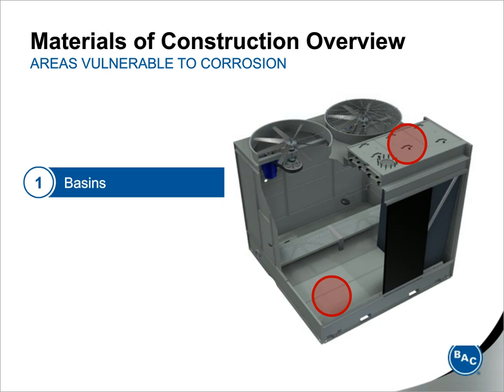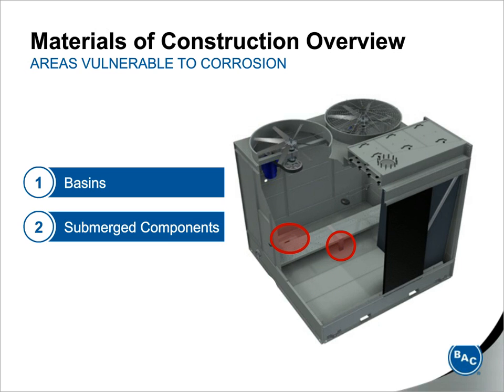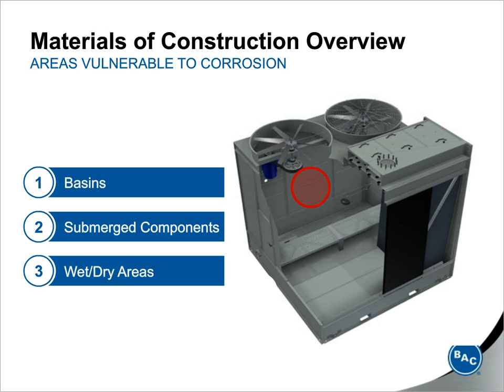When the cold water collection basin corrodes beyond repair, often it's actually more practical to replace the entire unit. Replacing the other panels is really not nearly as much of an issue as replacing the cold water basin panels. So protecting that cold water basin is absolutely critical to ensure the longevity of your equipment. The next areas that are susceptible to corrosion are any submerged components, so that would include supports and strainers. And then the areas that are least susceptible to corrosion are areas that aren't fully submerged in water, like casing panels and some structural members, but they are still vulnerable to corrosion.